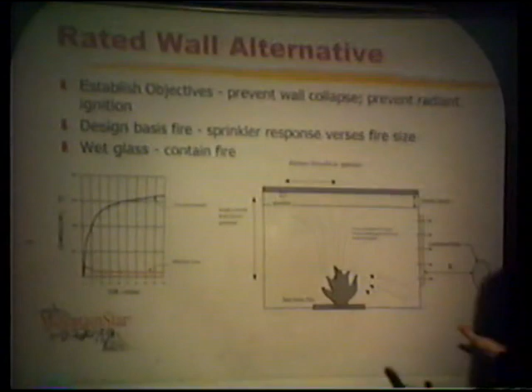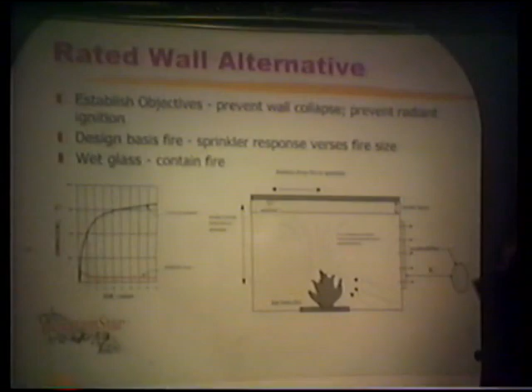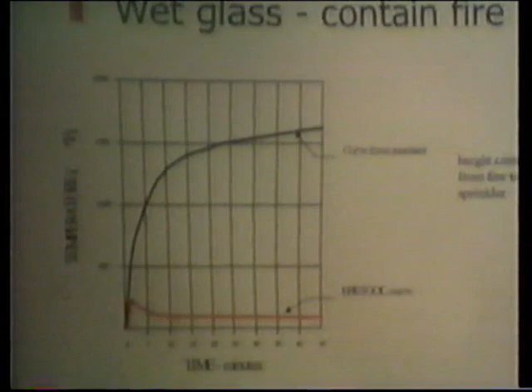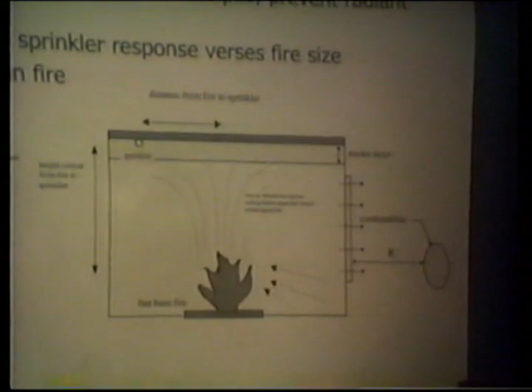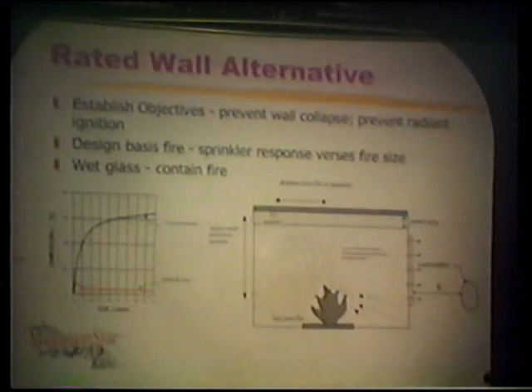You can also use it to eliminate rated walls or reduce the rating on rated walls, where rated walls have to follow a prescribed time-temperature curve. Well, we can show and demonstrate a very simple example of reducing the rating in a space, because if we put in a very aggressive active sprinkler system, the temperatures would never get to the point that would require the hourly ratings as defined by code. The question is, when you put all your eggs in an active suppression basket, you have to know about reliability and how reliable is that system. That's one of the Achilles heels of performance-based fire protection: knowing the reliability of these systems.